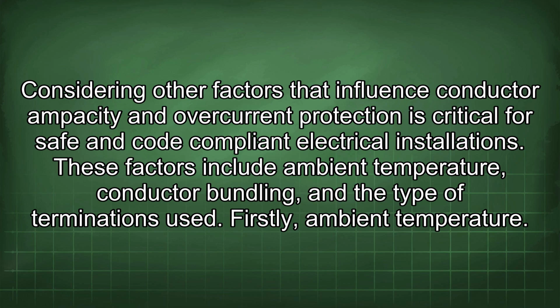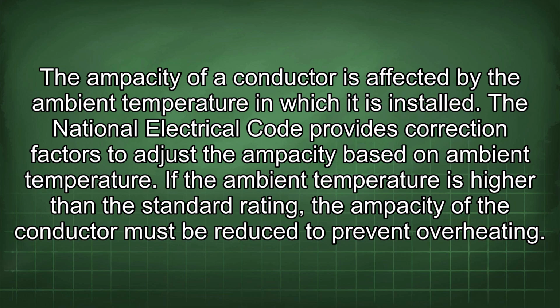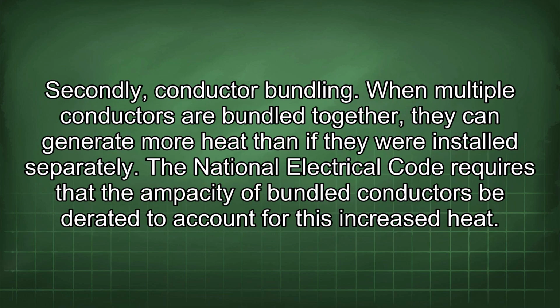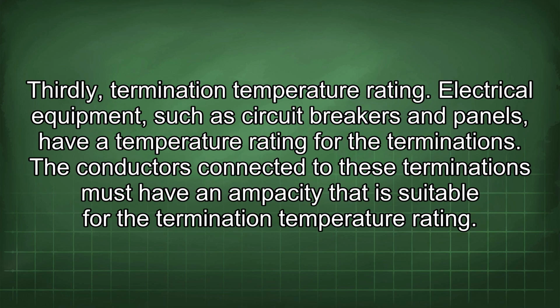Firstly, ambient temperature. The ampacity of a conductor is affected by the ambient temperature in which it is installed. The National Electrical Code provides correction factors to adjust the ampacity based on ambient temperature. If the ambient temperature is higher than the standard rating, the ampacity of the conductor must be reduced to prevent overheating. Secondly, conductor bundling. When multiple conductors are bundled together, they can generate more heat than if they were installed separately. The National Electrical Code requires that the ampacity of bundled conductors be derated to account for this increased heat. Thirdly, termination temperature rating. Electrical equipment, such as circuit breakers and panels, have a temperature rating for the terminations.